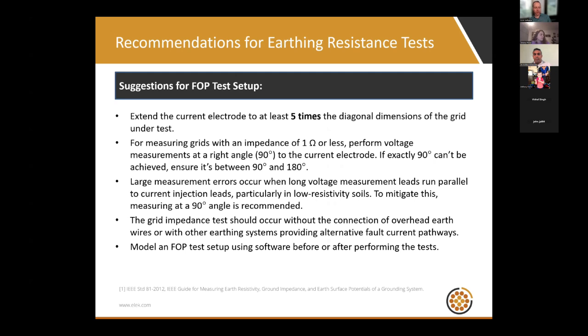Large measurement errors occur where you have long voltage measurement leads in parallel with current injection leads, particularly for low resistivity soils. To mitigate this, if you can, in a practical situation, run your voltage measurement leads at 90 degrees. The grid impedance test should occur without the connection of overhead earth wires, or other earthing systems connecting other pathways. You should minimize interference.